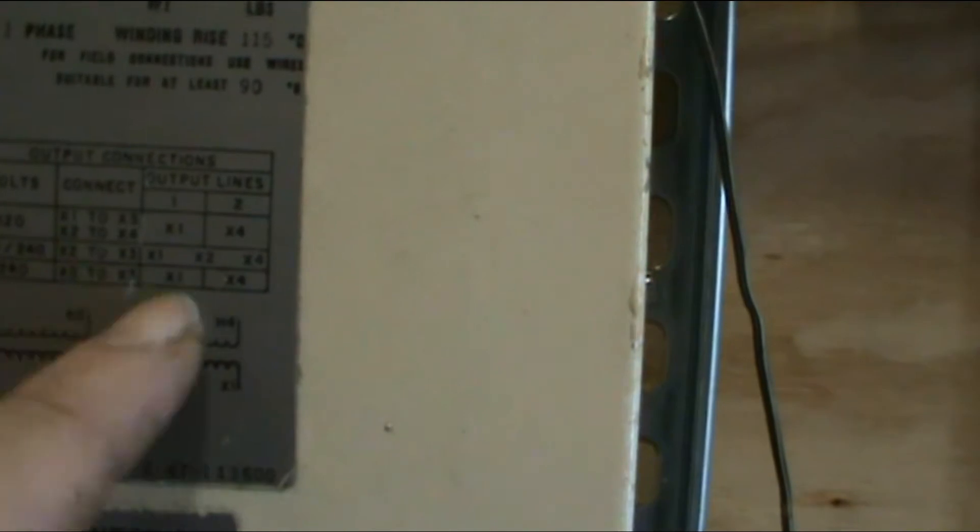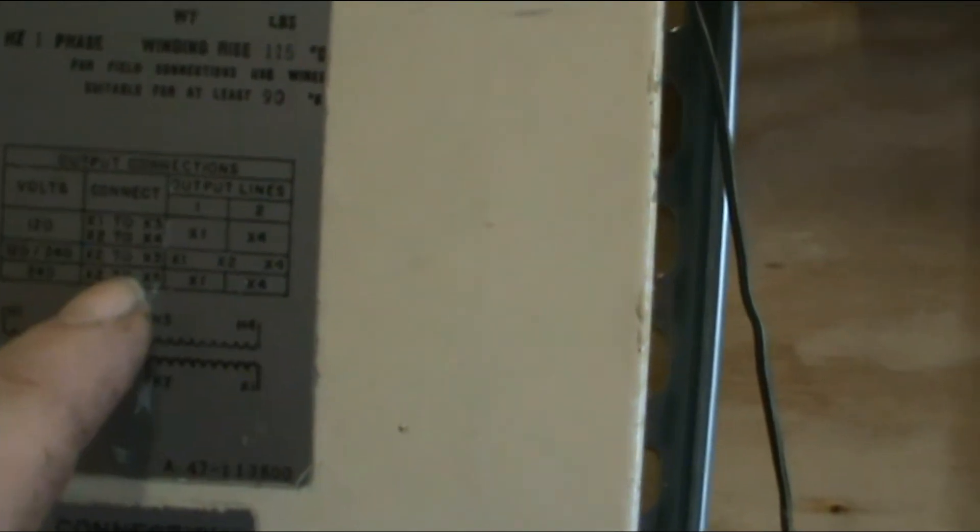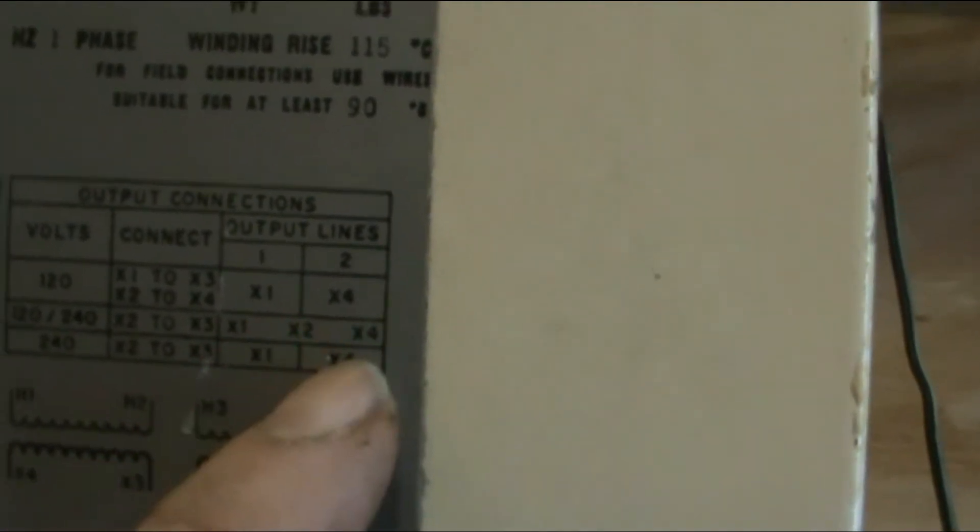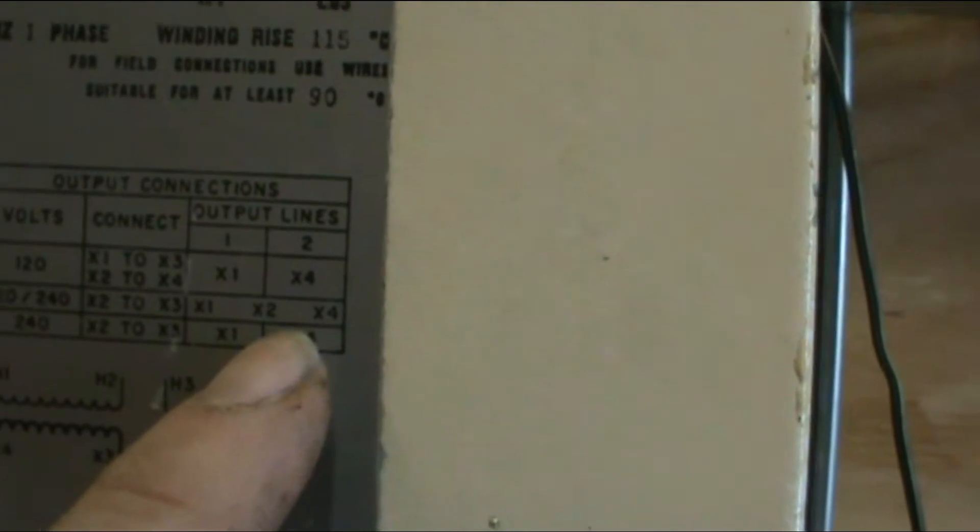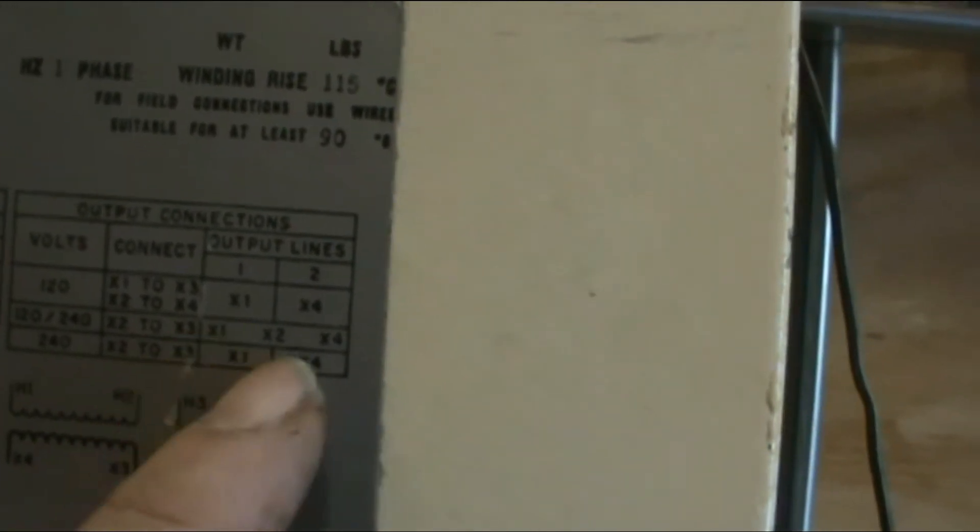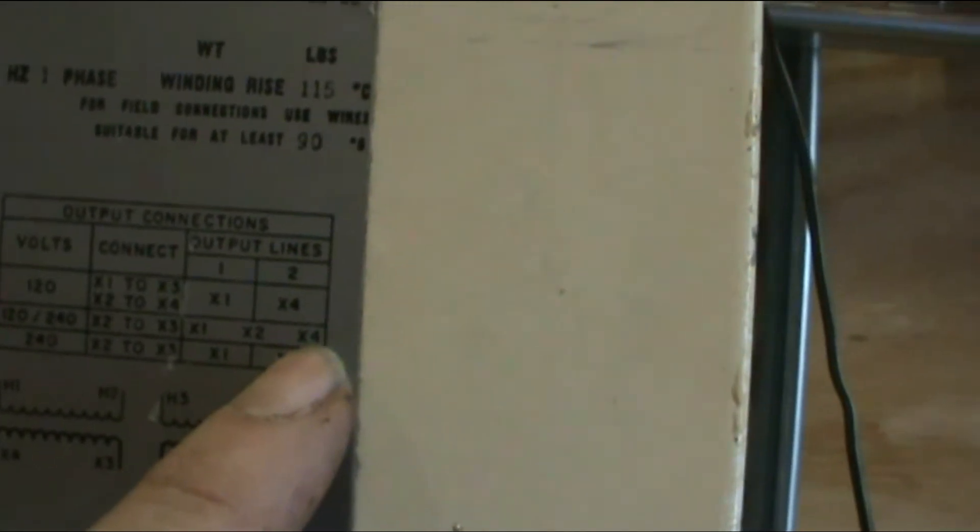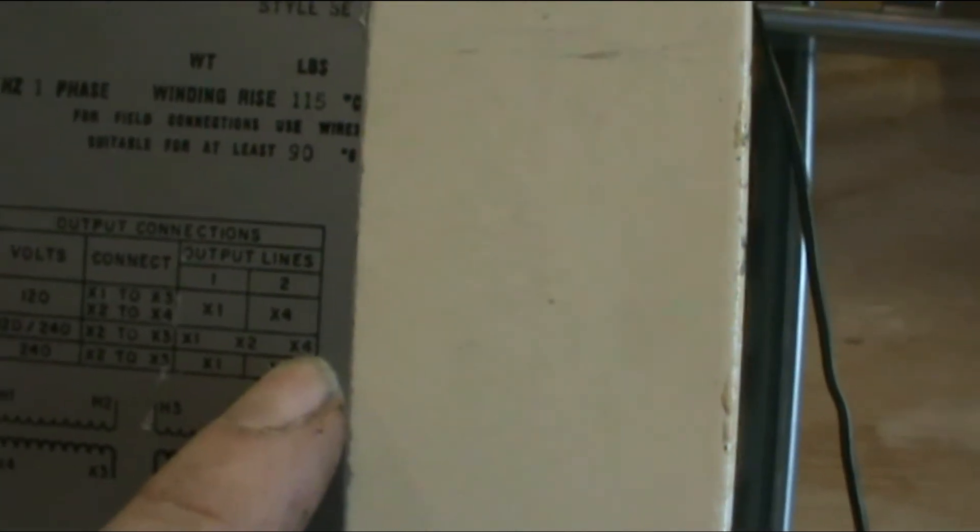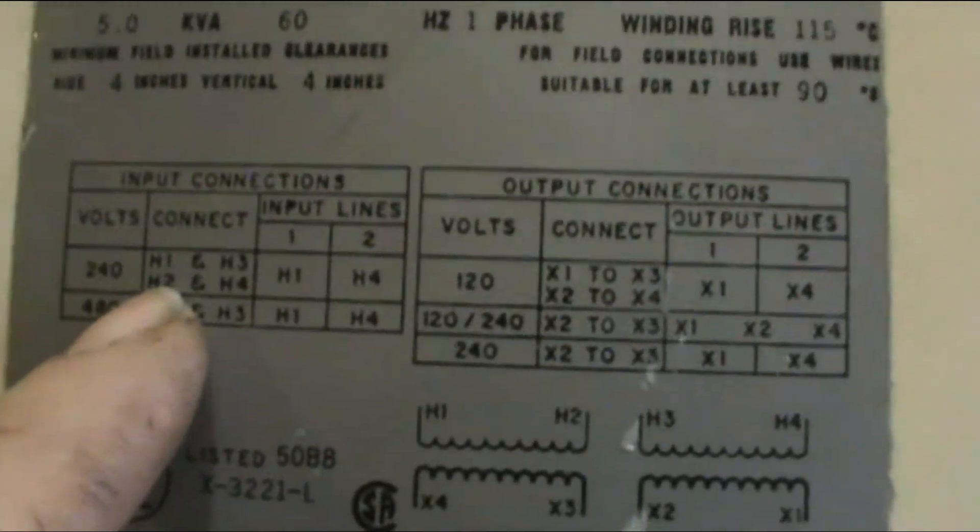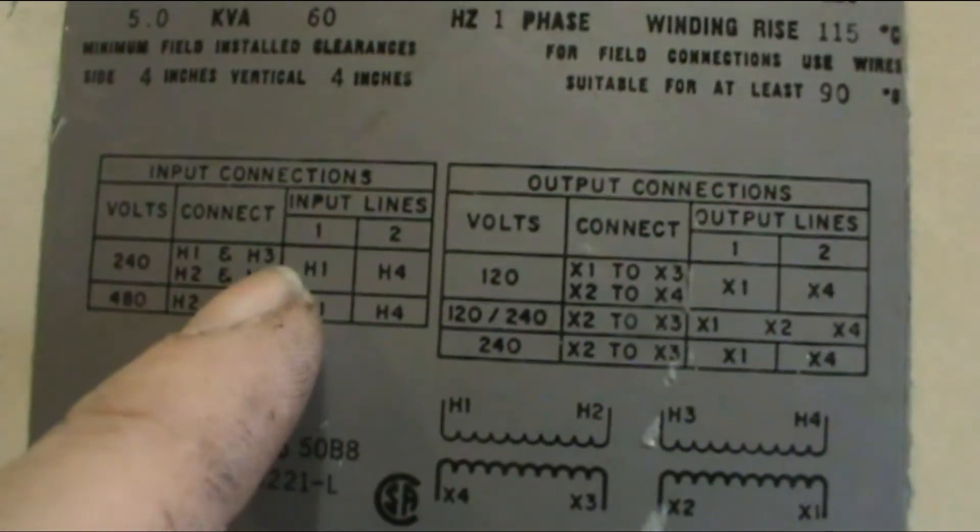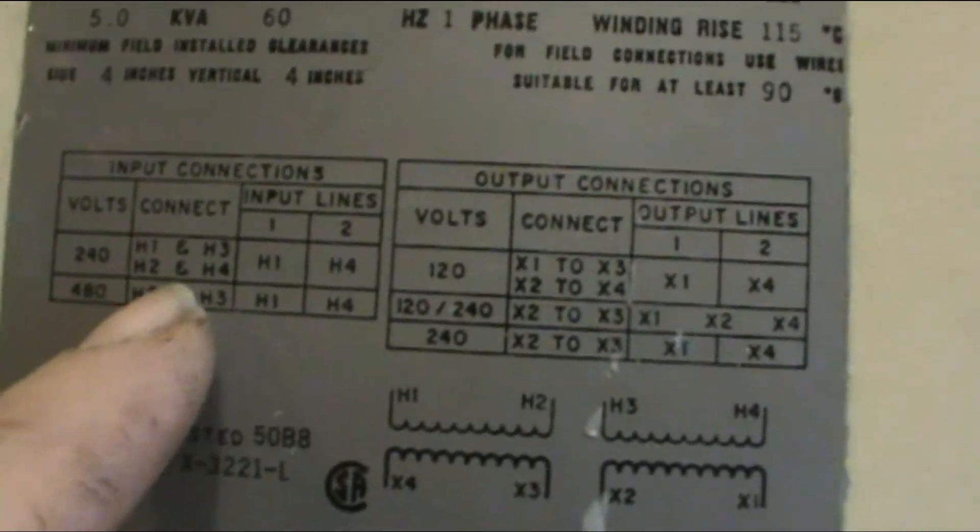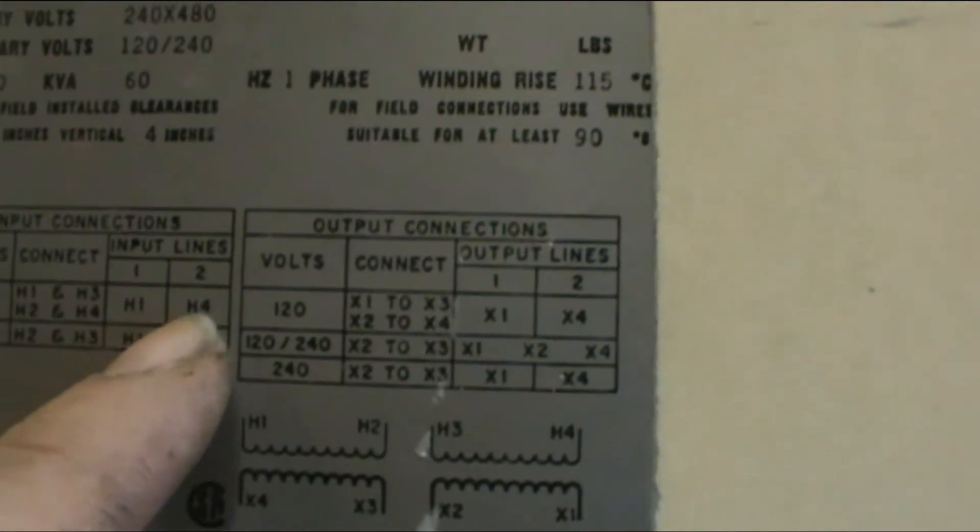The way you do this, you connect X2 to X3, wire those together. Here's your connections: X1, X2 and 3 wired together, and X4. So X4 to X1 is 240, X1 to X2 is 120, X2 to X4 is 120. There's your 240 volt split phase. I've got it wired for 240 volt input.